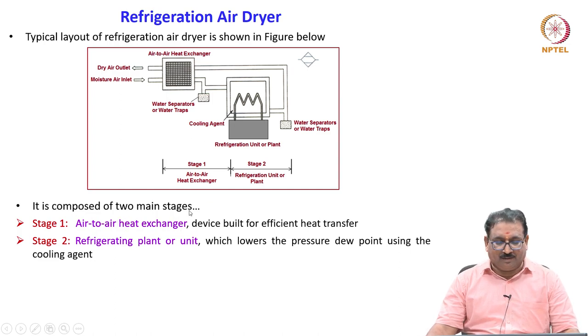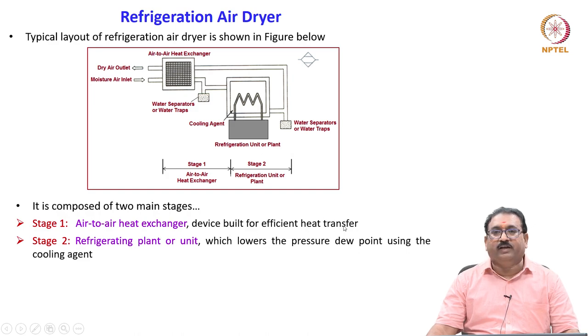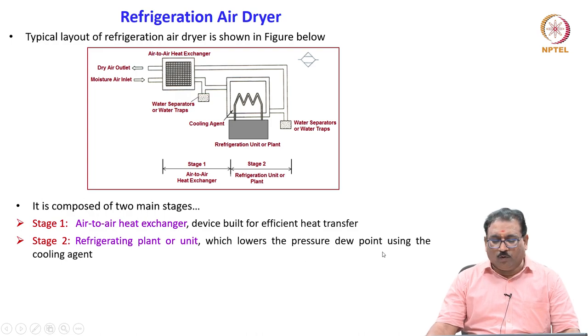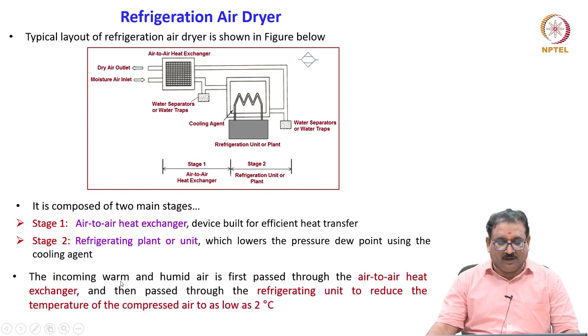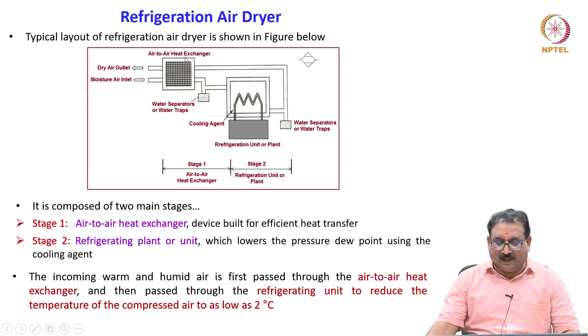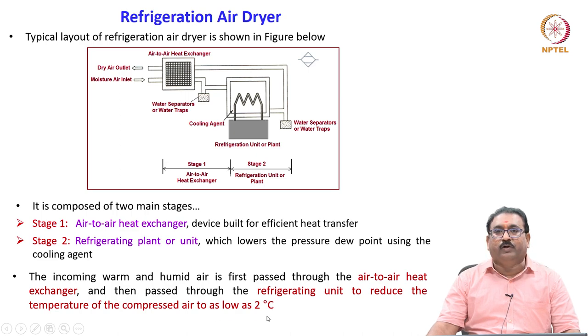It is composed of two stages: stage 1 and stage 2. In stage 1, the air-to-air heat exchanger is a device built for efficient heat transfer. Stage 2 is the refrigerating plant or unit, which lowers the pressure dew point using the cooling agent. The incoming warm and humid air is first passed through the air-to-air heat exchanger and then to the refrigeration unit to reduce the temperature of the compressed air to as low as 2 degrees centigrade.